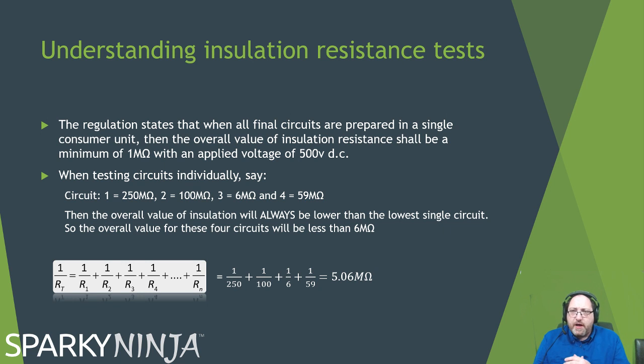Here's an illustration of the math. I'm testing circuits individually, and I've got 250 megohm, 100 megohm, 6 megohm, and 59 megohm. Now the formula: 1 over RT is 1 over R1 plus 1 over R2 plus 1 over R3, etc. This kind of math probably will be more in the 239455 and 239152 suite kind of course, but you do need to know about the rules of insulation testing, and that's illustrated here with this formula. When I use the formula, you'll notice that the lowest resistance of the single circuits measured is 6. When I then combine them all together for a single measurement, by doing the math here, 1 over RT, the overall resistance value now has come below 6. So the overall value of insulation resistance is always lower than the lowest single circuit value.